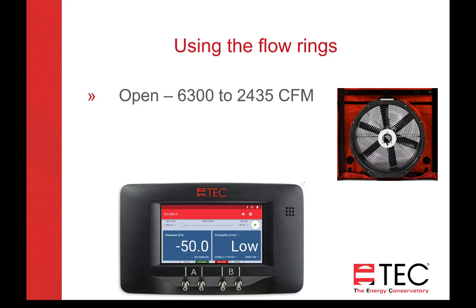The gauge is always reading a pressure. In this case it's reading the pressure at the flow sensor of the fan, and it's converting it to flow based on which device you chose and which ring configuration you chose. If that pressure at the flow sensor is below 26 pascals, then it's going to show low, and you need to add rings.